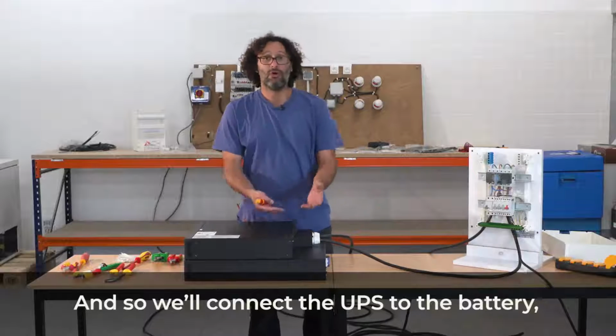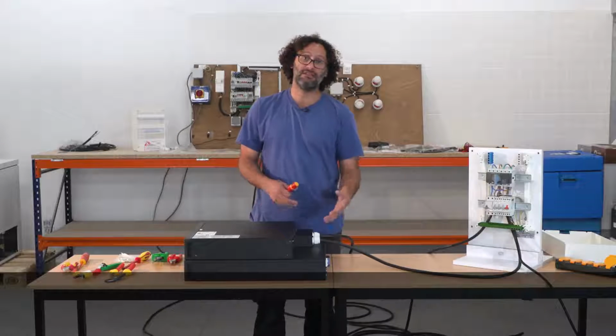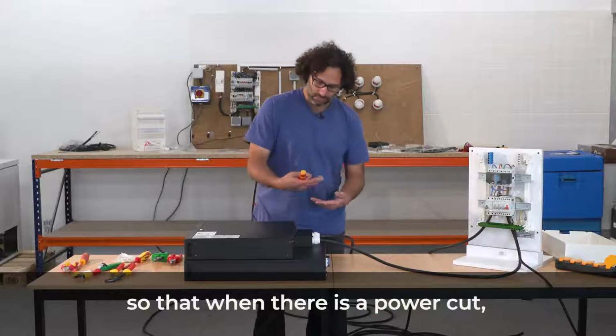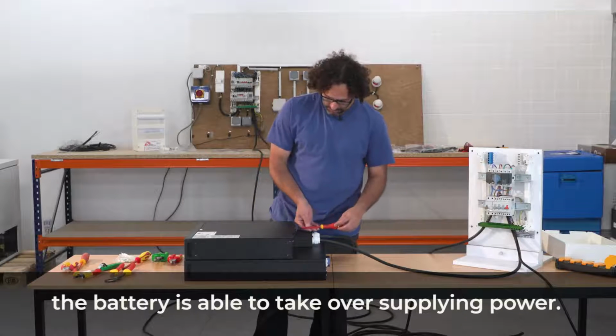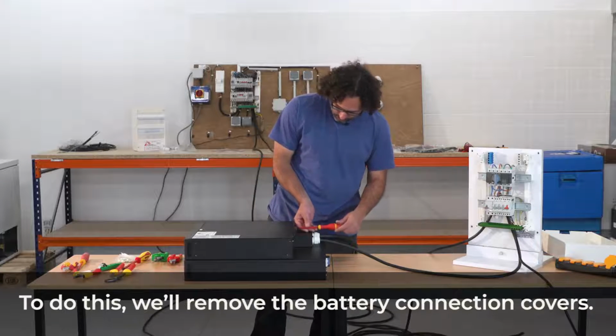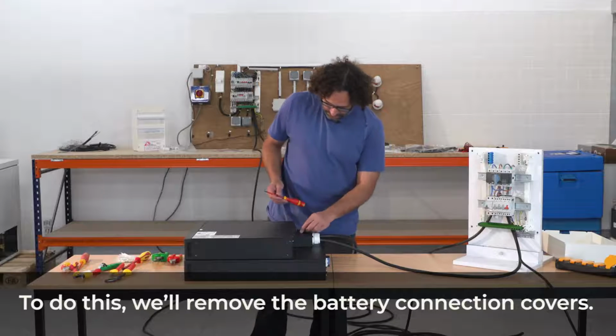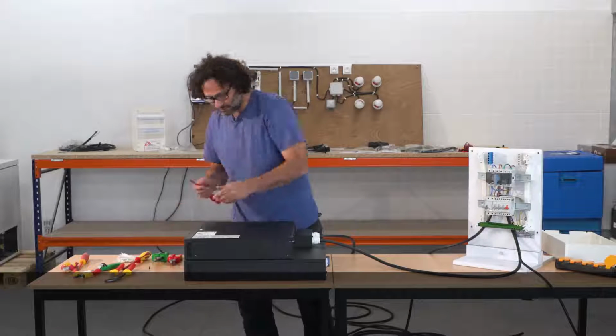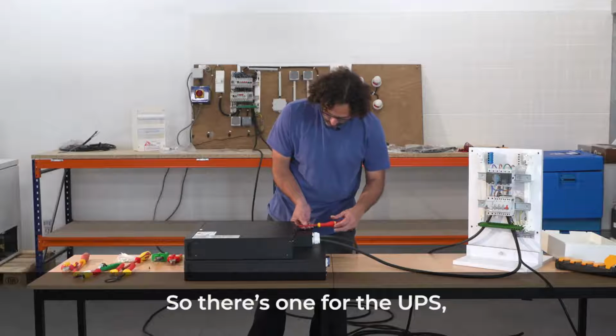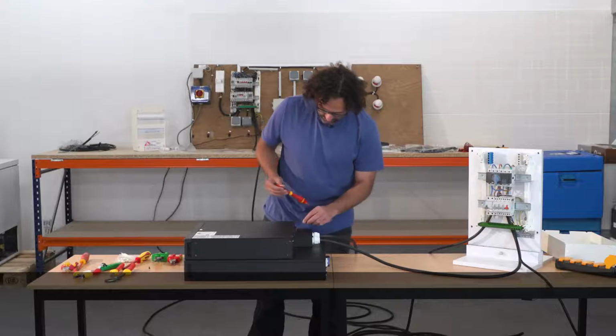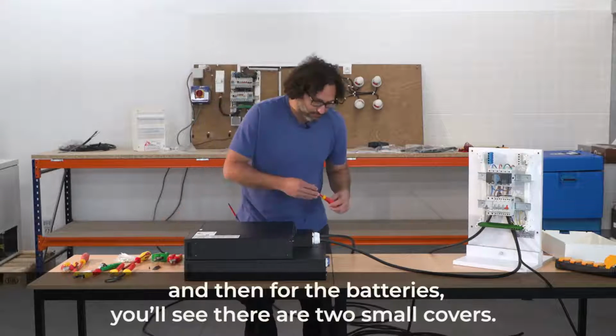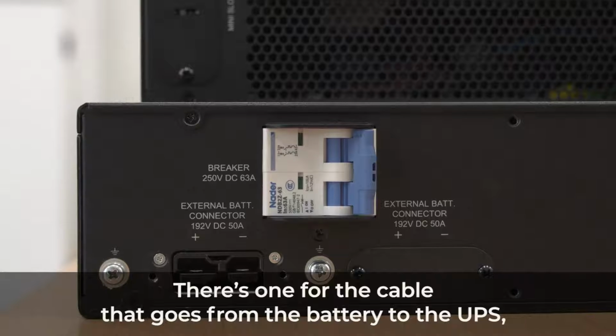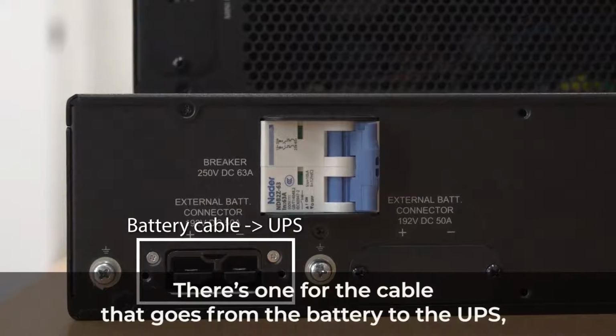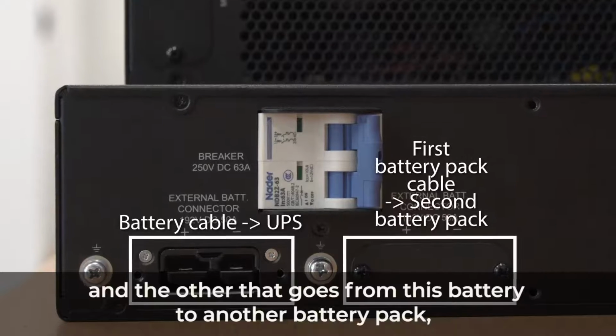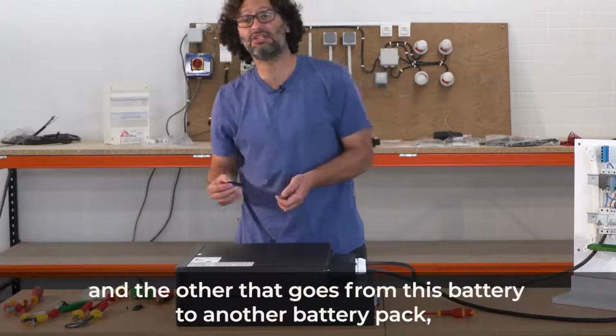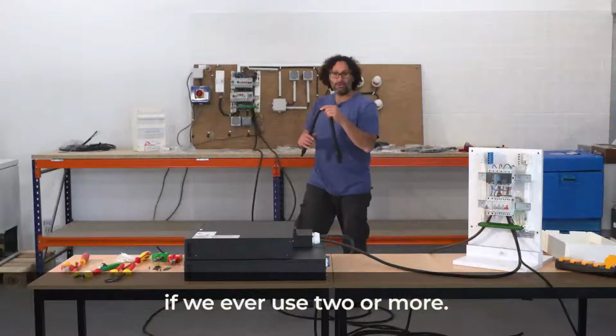And so we'll connect the UPS to the battery so that when there is a power cut, the battery is able to take over supplying power. To do this, we'll remove the battery connection covers. So there's one for the UPS, and then for the batteries, you'll see there are two small covers. There's one for the cable that goes from the battery to the UPS, and the other that goes from this battery to another battery pack, if we ever use two or more.